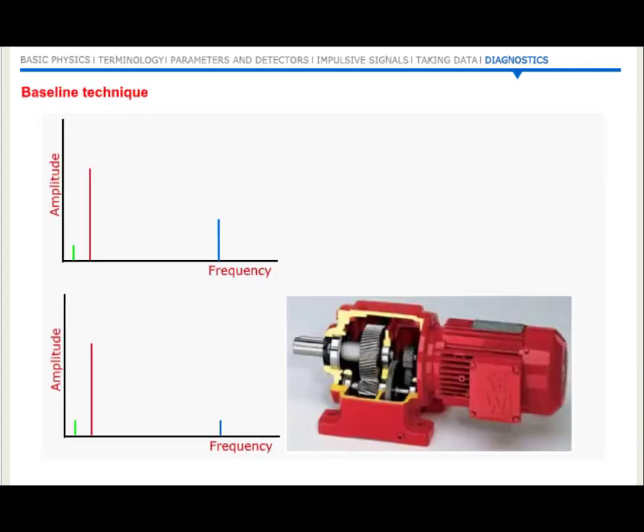If we observe an amplitude increase at a frequency, then we know that the forces have increased and we can diagnose which component inside the machine is at fault. A common way of using this data is to use the baseline technique. The baseline is the spectrum from a machine in acceptable condition. When the monitoring process indicates that significant change has occurred, a new spectrum is prepared and compared with the baseline. It's the differences that tell the story. In this example, we can clearly see that it is the high-frequency vibration from the gear mesh that has increased.